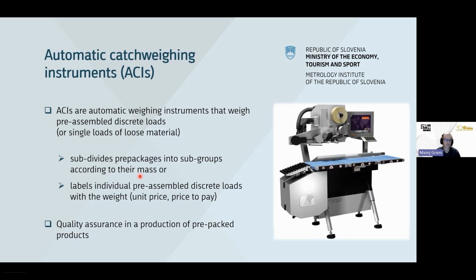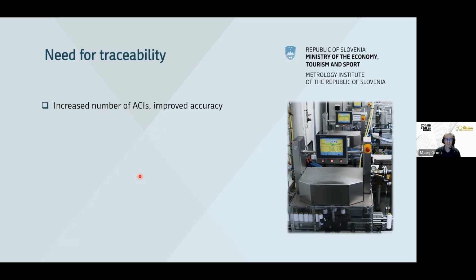So it is very important to provide suitable quality of measurements on these instruments, and there is strong need to provide traceability. The number of these instruments nowadays in the industry is very high, and it is very important that these instruments are not only used for legal metrology purposes. In legal metrology, we know that instruments require type approvals, require verification, but there is a large group which is not subject to legal metrology, and it is essential also to provide in this field proper traceability.